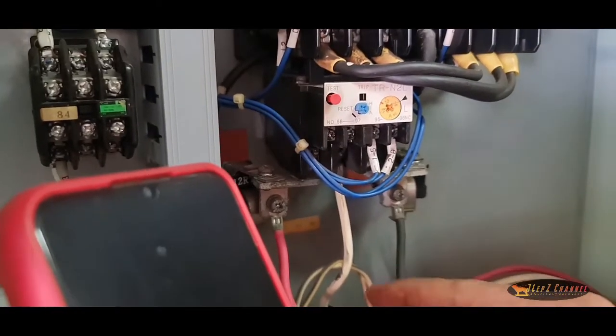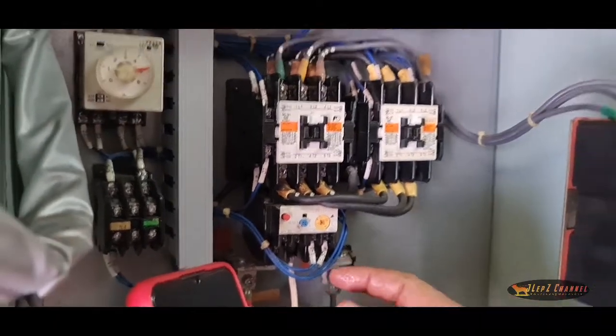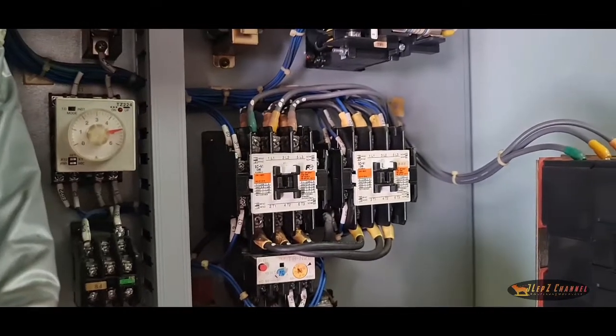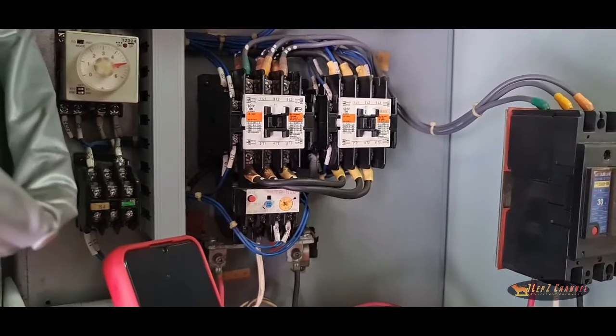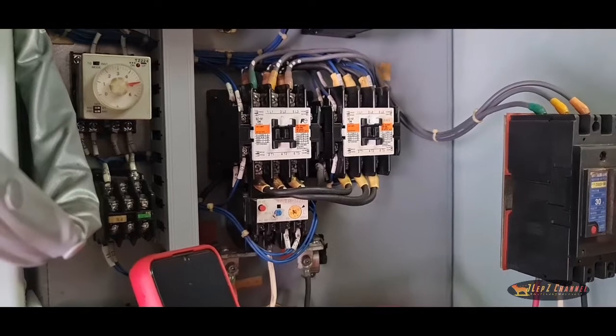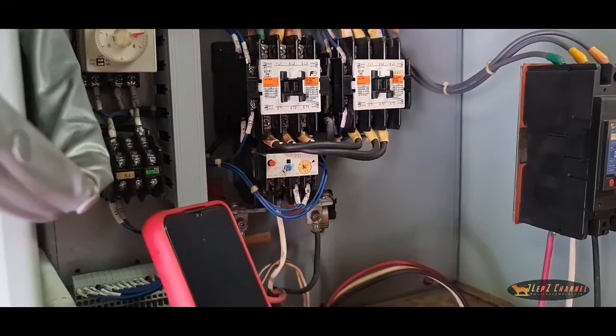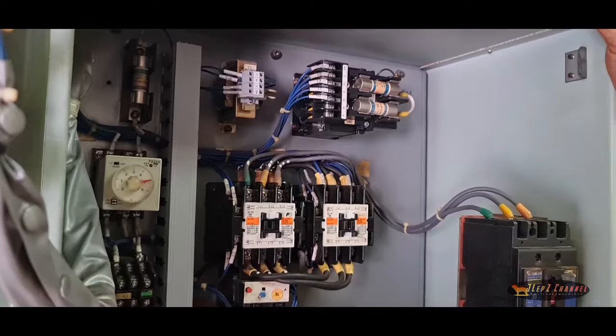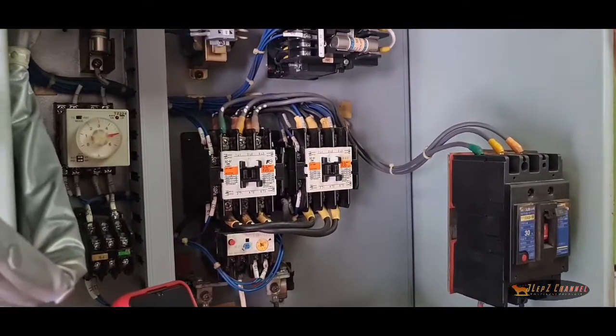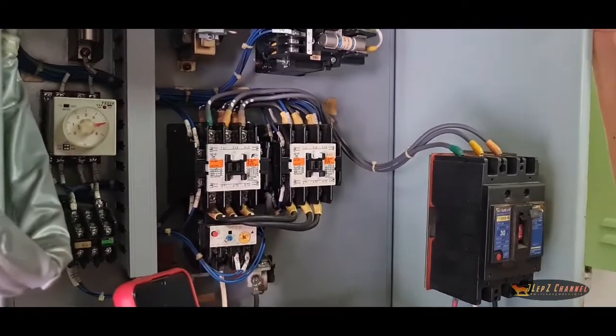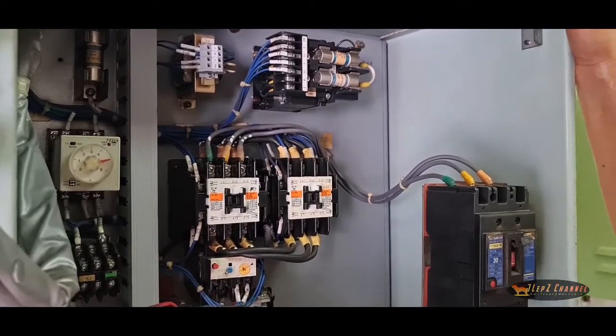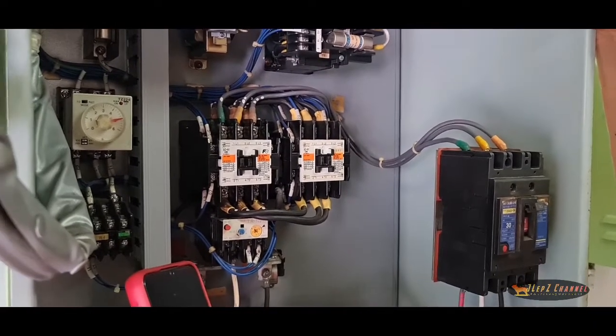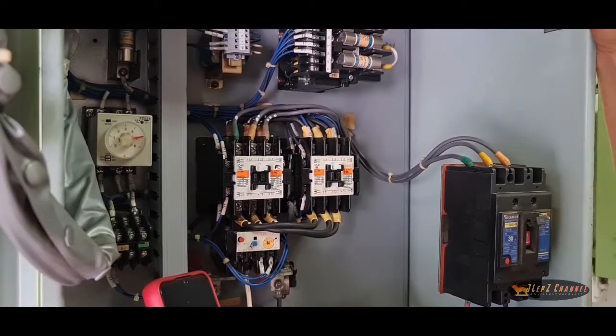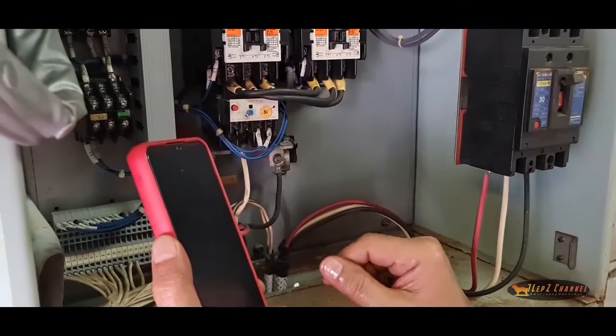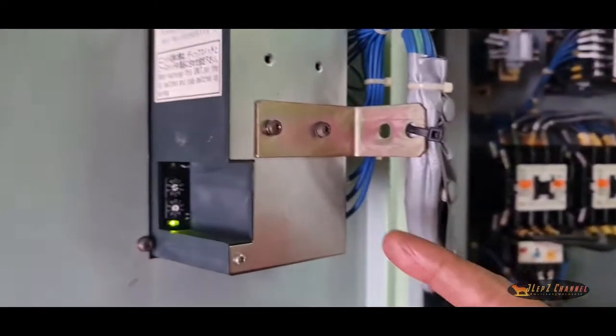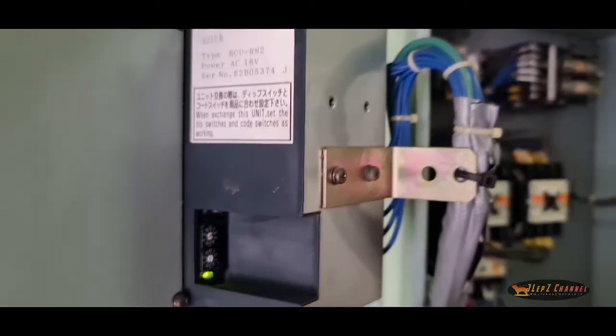And our highest reading is 21. Now we set this to 26, far below the 29 maximum, so I think it is still safe. We set it to the maximum 26 because the engine room fan motor is always tripping. It was tripping every time there was testing of the ballast pump. But when the ballast pump is not running or starting, this engine room fan doesn't trip off. Anyway, with this engine room fan, you don't need to come here to reset because we have an electronic control type. It starts by itself and it resets also by itself.